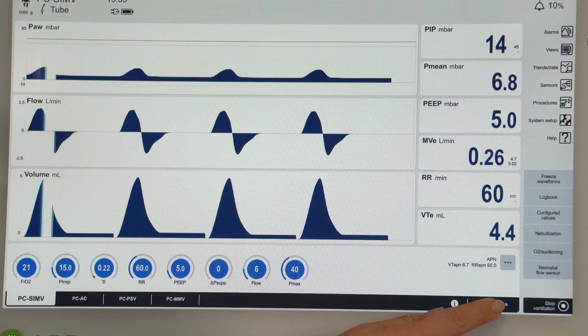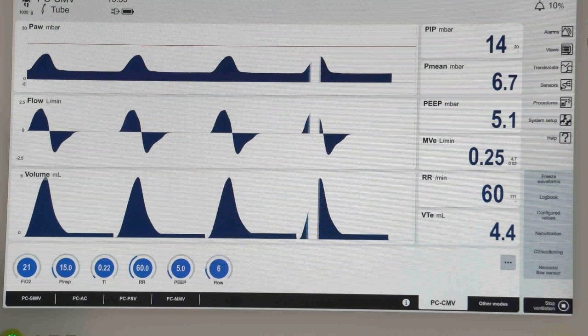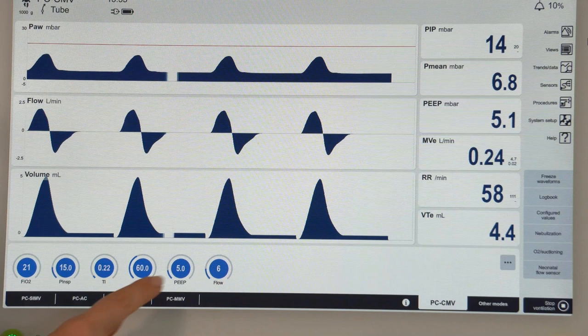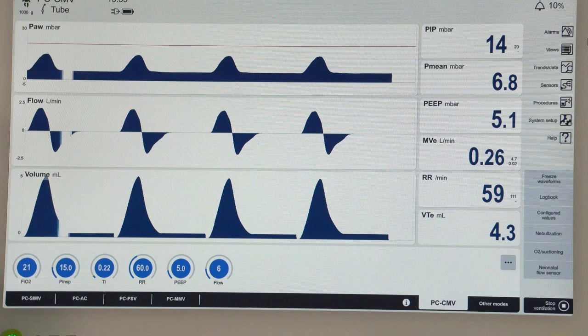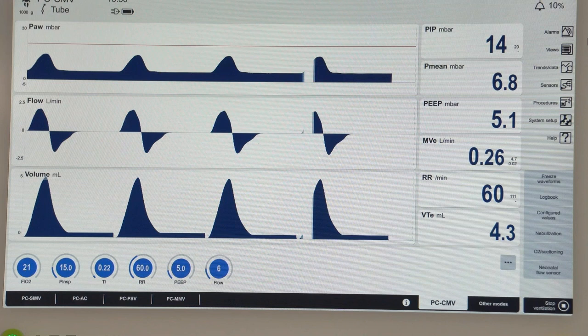We are now in pressure-controlled continuous mandatory ventilation (PC-CMV) mode — completely mandatory ventilation where we have 60 breaths per minute delivered with an inspiratory pressure of 15 and PEEP of 5. The ventilator delivers this breath-by-breath regardless of the patient's breathing efforts. This is how mechanical ventilation for neonates has been done in the past.